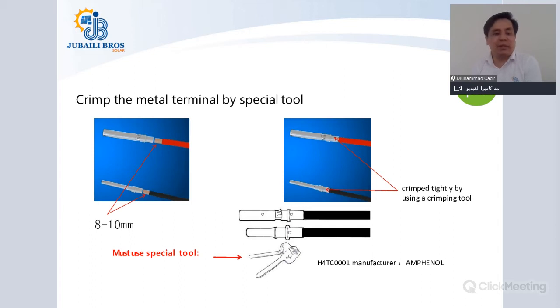Otherwise, this may lead to a loose connection due to the wrong use of the tool, and loose connections can lead to sparking at the connection points, which can damage the inverter. Also, if you open the user manual, you will see the insulation length which you should be cutting to join it with the connector. So as you can see in the picture on the left side, for one of our inverters, we are advising you to have around 8 to 10 mm of your insulation cut to put it into the connector. So use the right tool and make sure that the insulation cut is according to the user manual guideline.